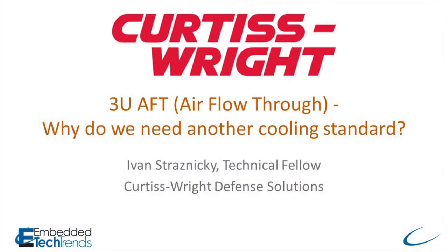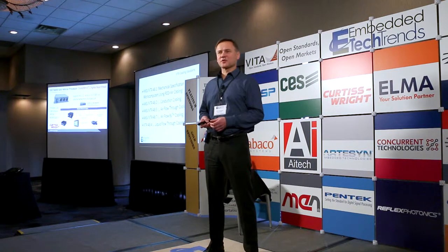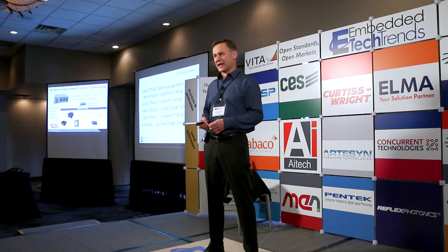I'm going to be talking today about a new VITA standard that we're introducing focused on 3U AFT, or air flow through. Some of you might know that there are existing standards already in VITA that have to do with cooling. We've got ANSI VITA 48.1 and 48.2, which are the incumbent cooling approaches for air cooling and conduction cooling respectively. There's ANSI VITA 48.5, which is an existing AFT cooling approach, and I'll be talking about the differences between what we're introducing today and that ANSI standard.